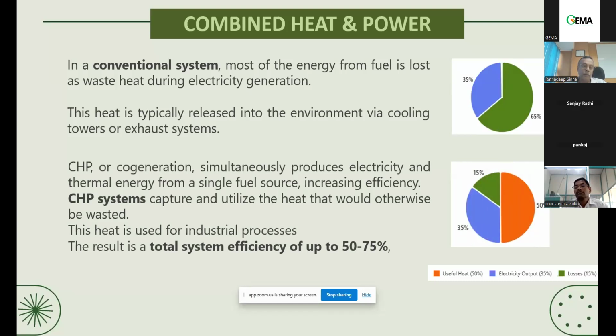However, when you talk about CHP, basically a cogeneration plant, you will find around 50 to 60% useful heat, or sometimes if cogeneration is more, 70-75% useful heat can be used. There will be certain losses, around 15% to 20%, and electrical power output will be 35%. So steam generation and power generation happen simultaneously, enhancing the overall capacity and efficiency of the power generation and cogeneration system.